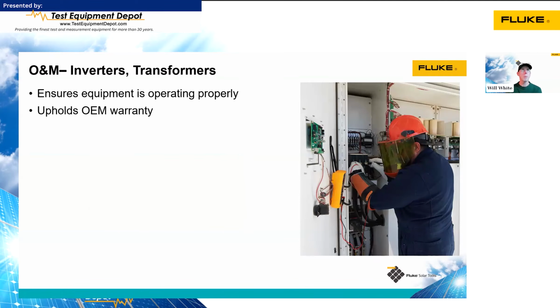We need to do this operations and maintenance on our inverters and our transformers because we want to make sure that the system is working properly. So we need to make sure that we're producing the amount of energy that we're expecting. Also, many manufacturers' warranties require regular maintenance. So we need to do that maintenance to uphold that warranty. If we don't do that maintenance, it will sometimes void the warranty. It's preventing system failure. So a properly maintained system will operate better than others. It will also maximize that production.